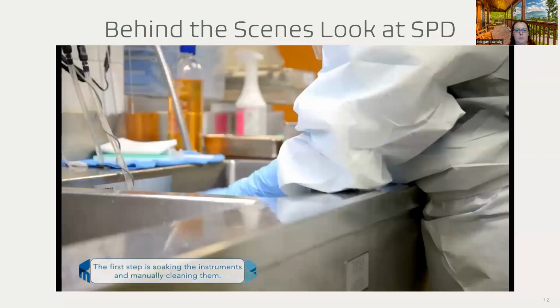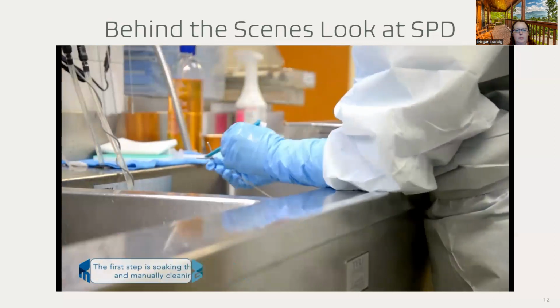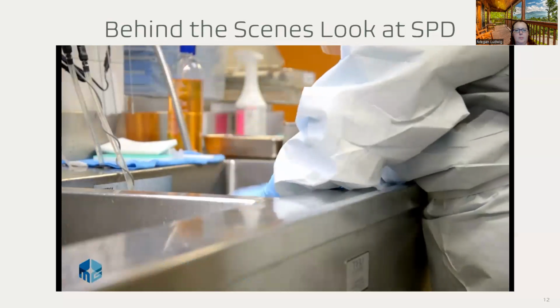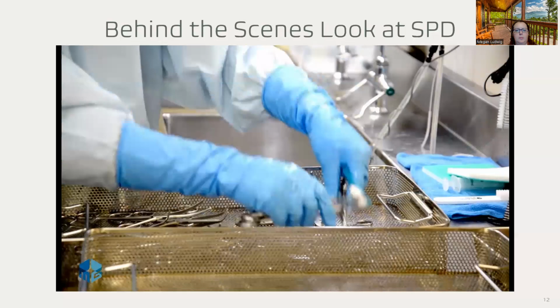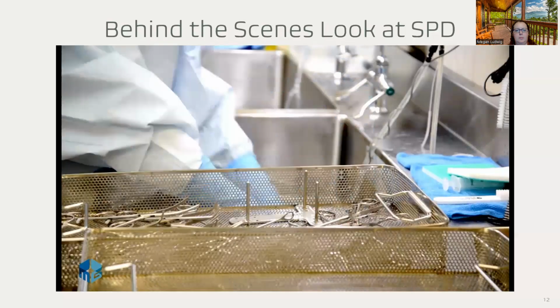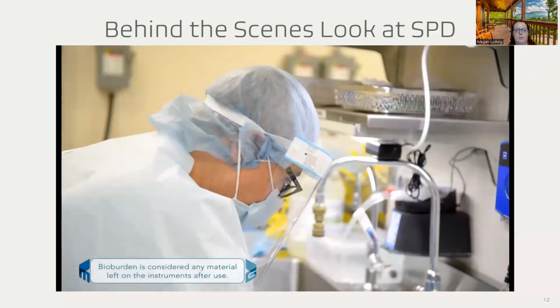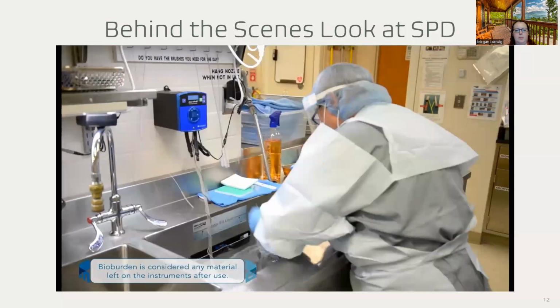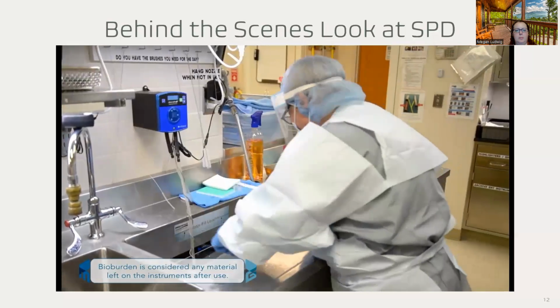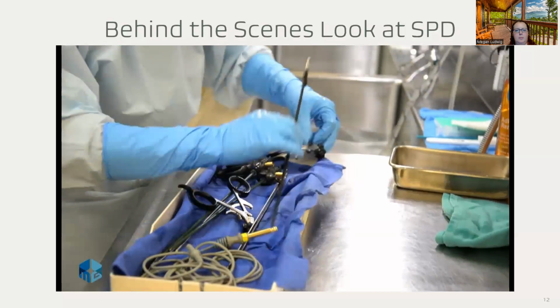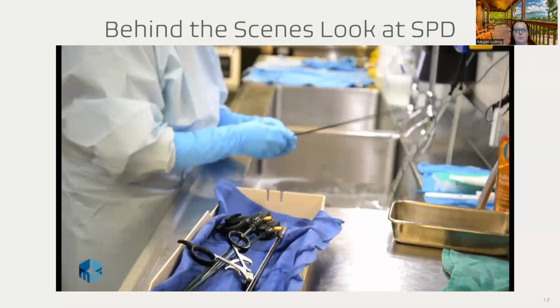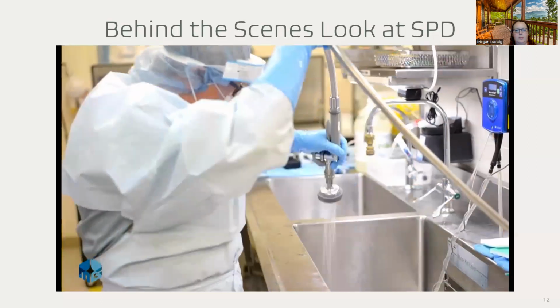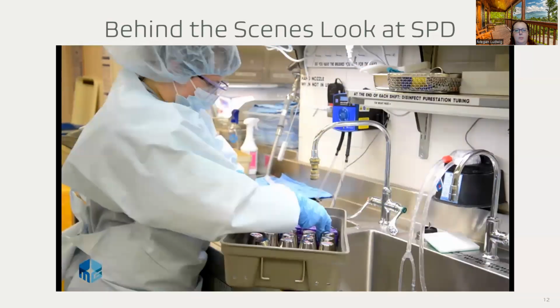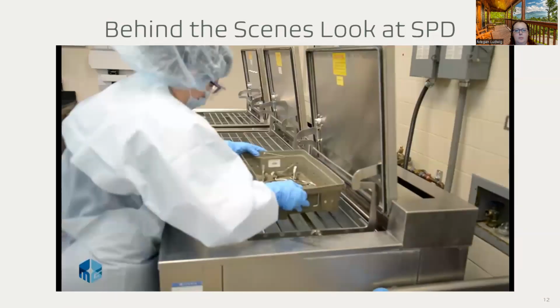This process begins by soaking and manually cleaning each instrument in a sink filled with a water and detergent mixture. This helps break down and remove the blood and other materials that can be left from surgery. We call this material bioburden. We use a variety of different types of brushes, syringes, and automated irrigators to remove the remaining bioburden from the instruments. After all the bioburden has been removed from the instruments, we rinse them and move them to the next step in the process, ultrasonic cleaning.